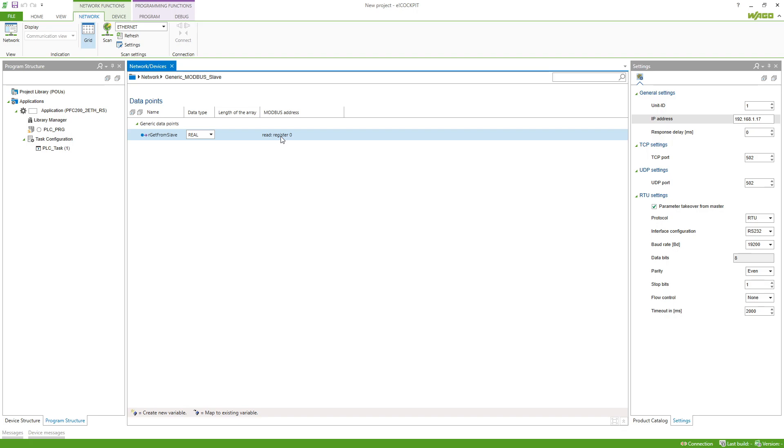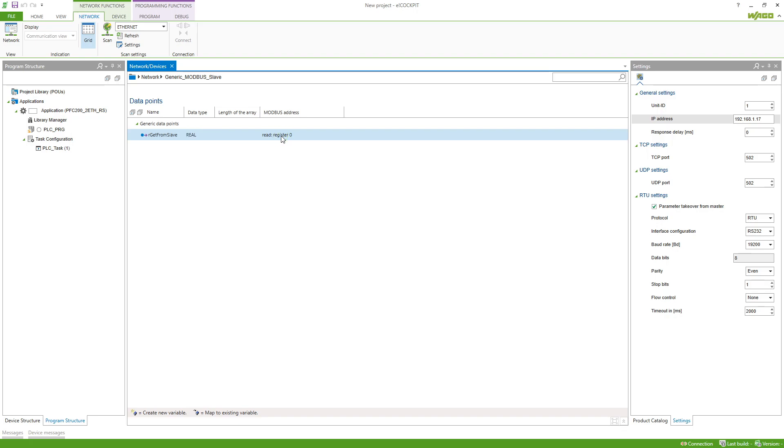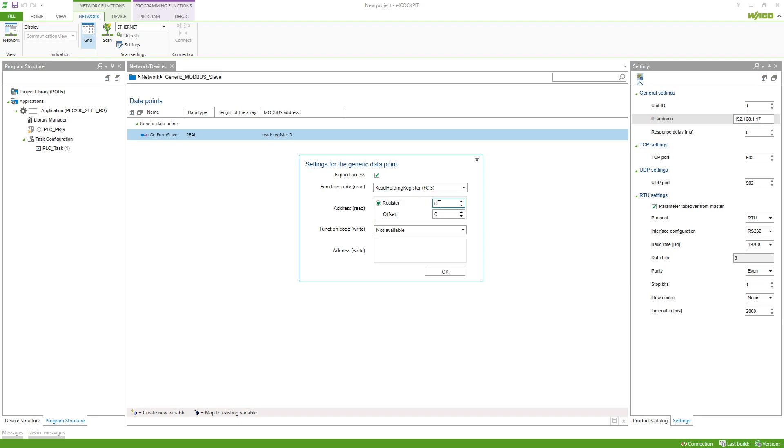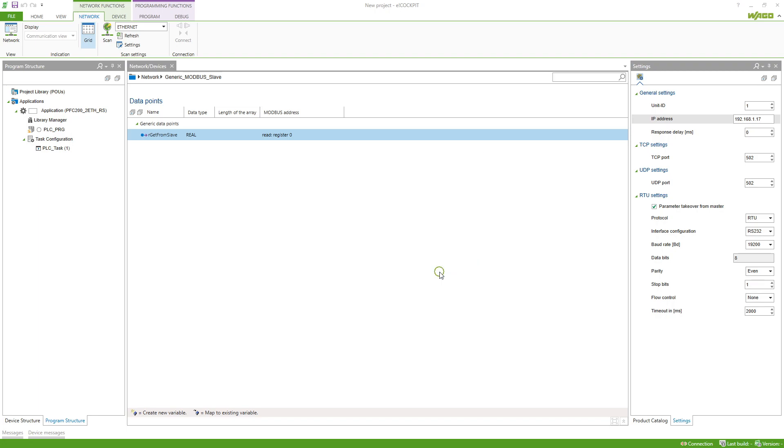The data type in my case is real and we want to read this. If I do a double click on the Modbus address we get the window where we can set the function code for Modbus. In this case function code 3 is fine and the register is 0 for me which is fine too. Writing is not available, this is correct, so I hit OK.